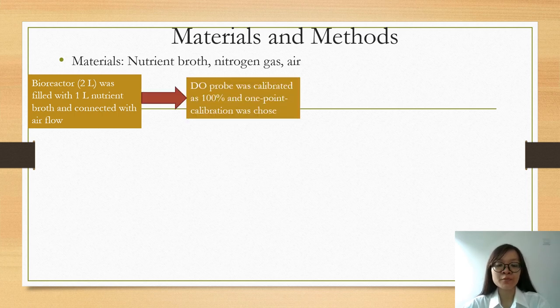Next, the one-point calibration was chosen and the optical DO-probe value was calibrated as 100% when the measured value was at a stable display.